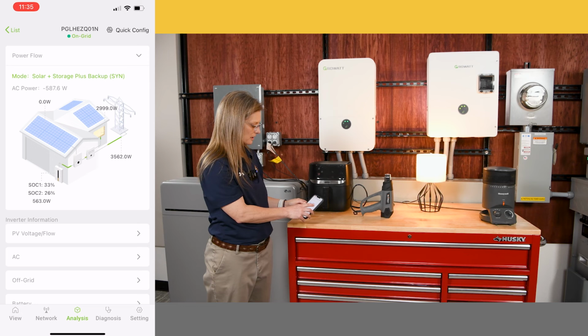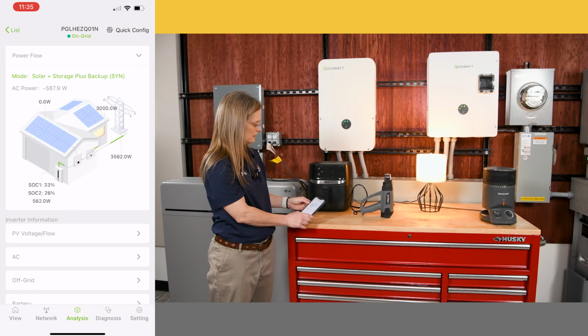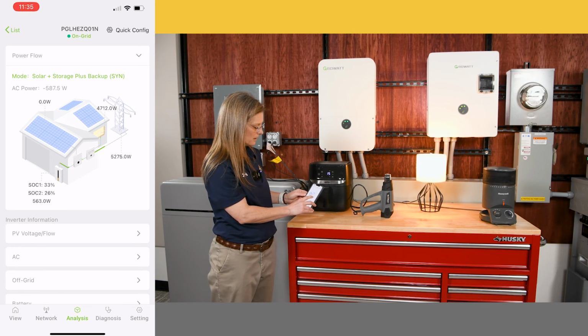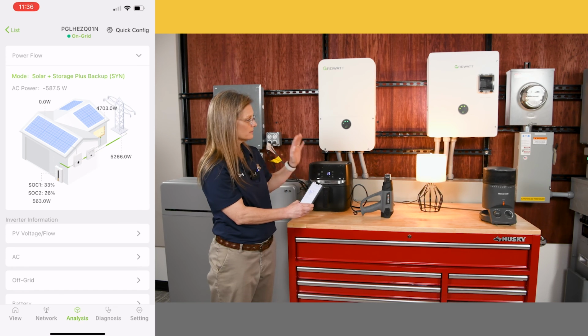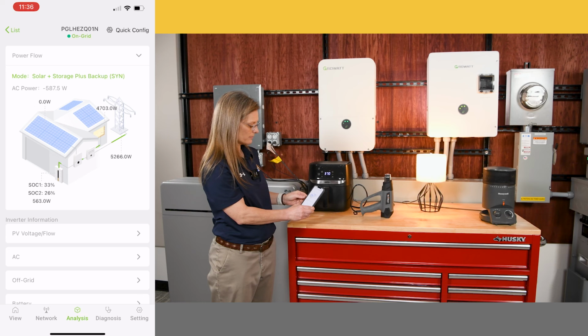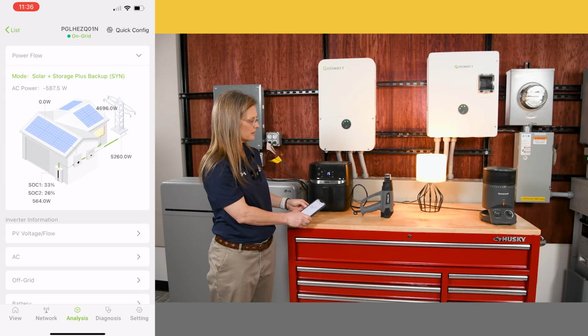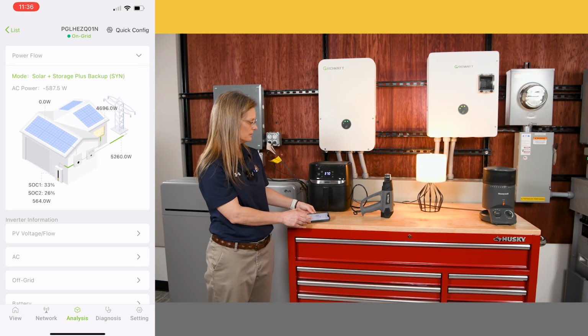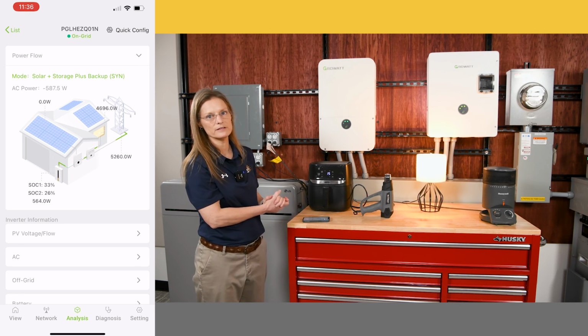What we're going to do is we're going to cut off all grid power, and we're going to watch our light and see what the cutover time is. Okay, we are actually pulling over 5,000 watts, 5,275 watts from the grid. A little more than 4,700 watts are going to our loads, and we have about 560 watts going to charge our batteries. So we're going to cut off our power from our grid and pull all of the power from our batteries. We're going to look at the light to see what our cutover time is, switch over, and see if our air fryer turns off or if it keeps going.